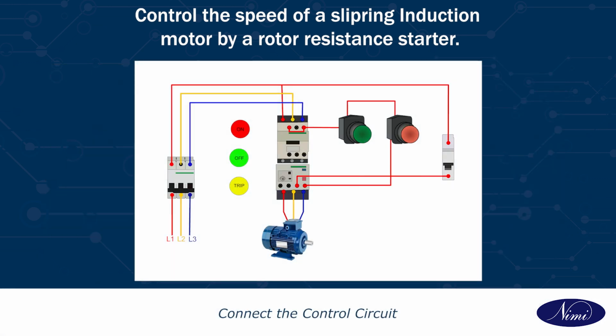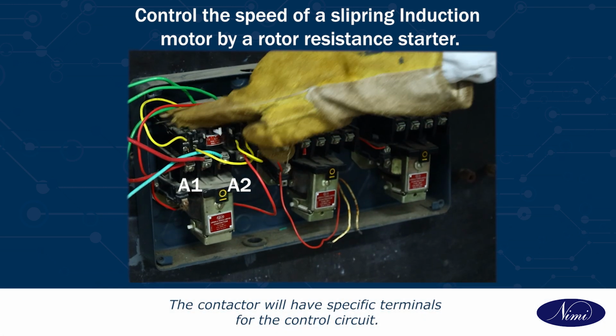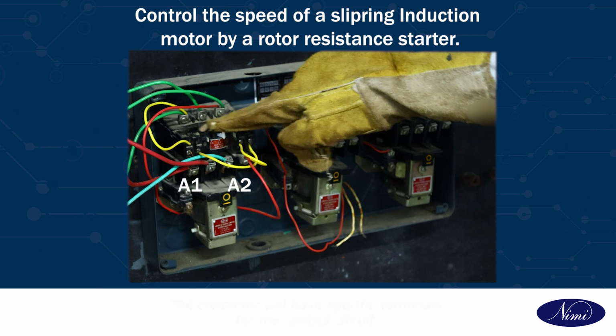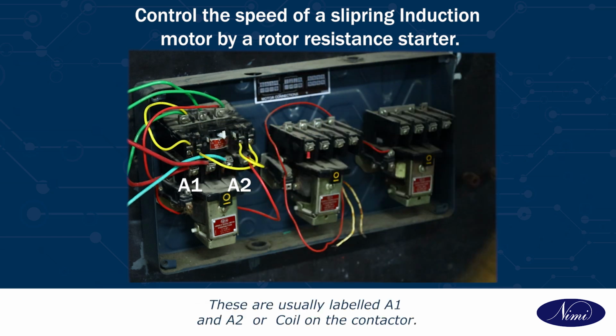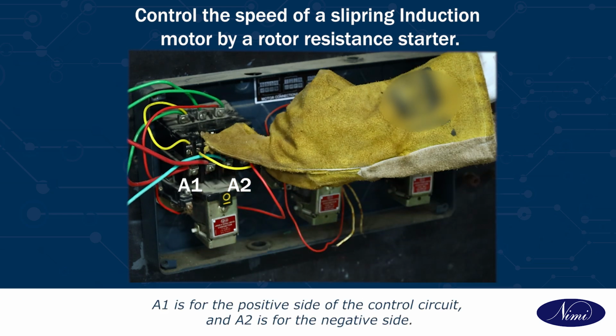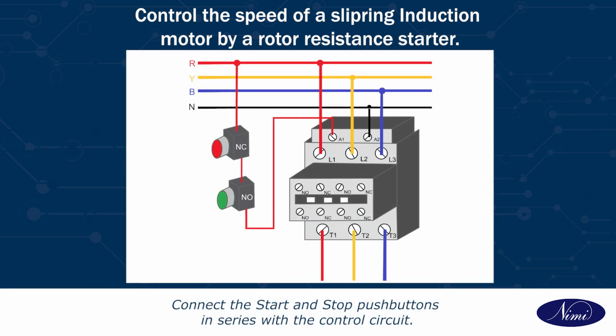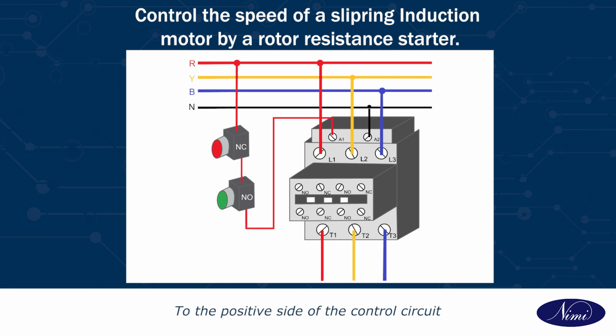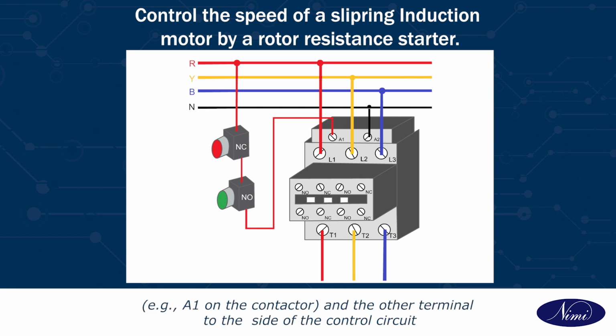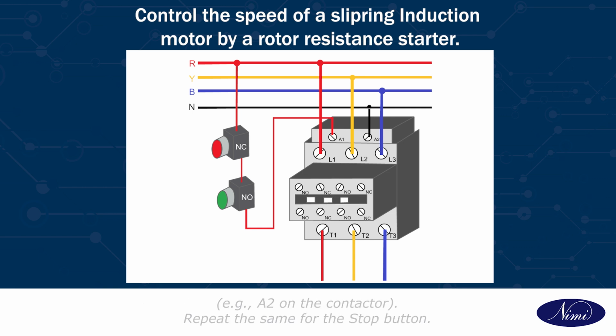Connect the control circuit. The contactor will have specific terminals for the control circuit. These are usually labeled A1 and A2 or coil on the contactor. A1 is for the positive side of the control circuit and A2 is for the negative side. Connect the start and stop push buttons in series with the control circuit. Use control cables to connect one terminal of the start push button to the positive side of the control circuit, example, A1 on the contactor, and the other terminal to the negative side of the control circuit, example, A2 on the contactor. Repeat the same for the stop button.